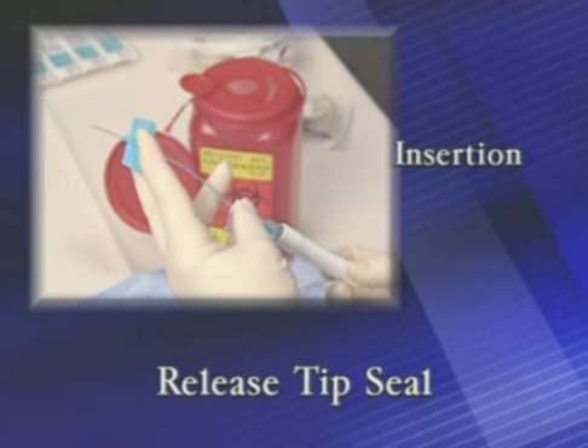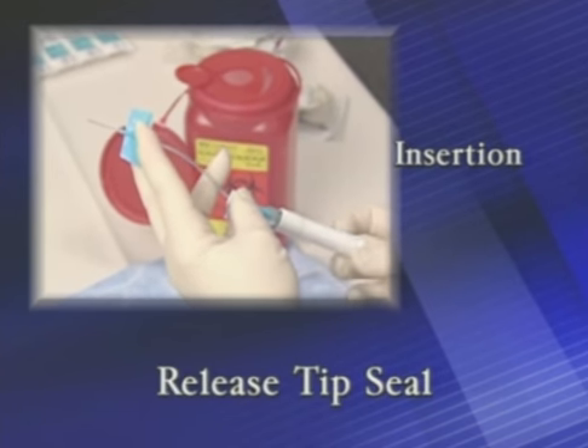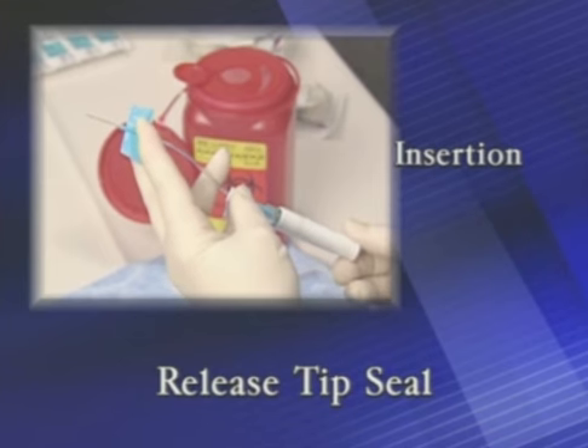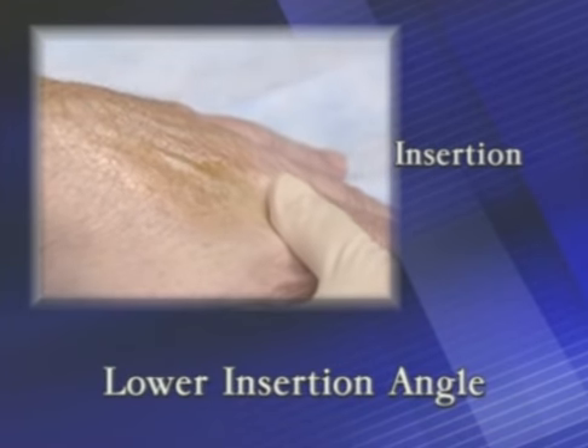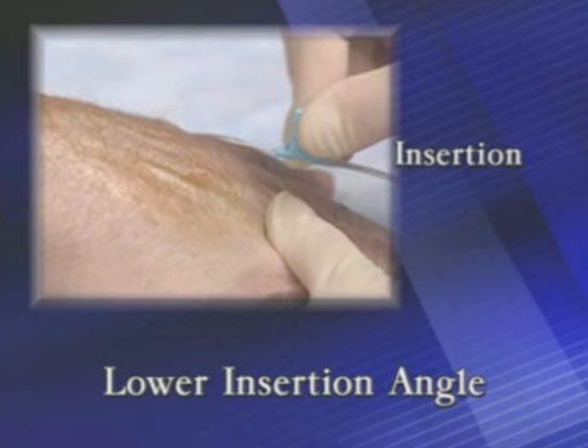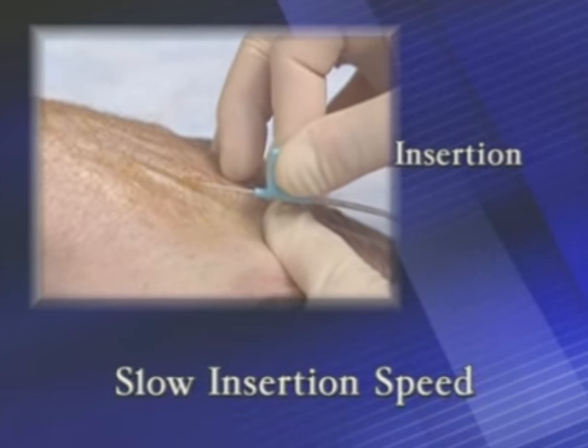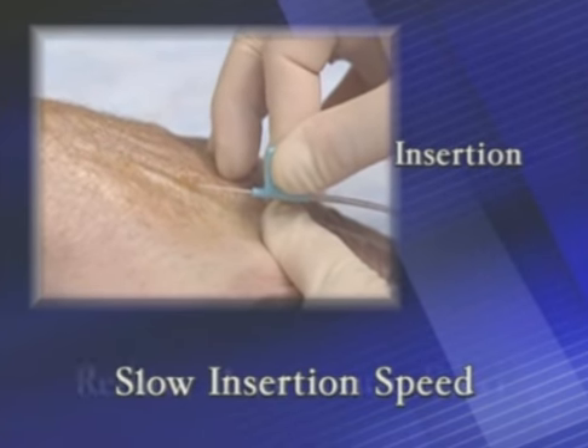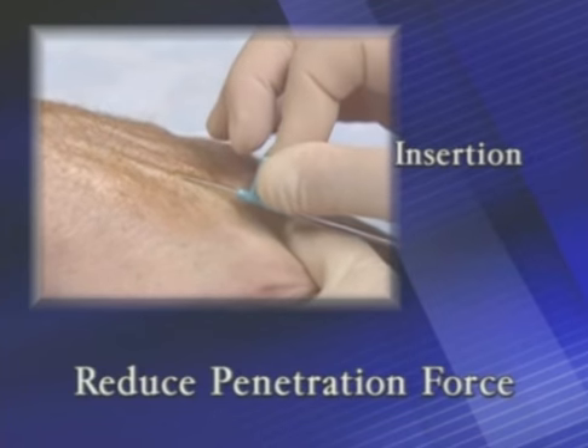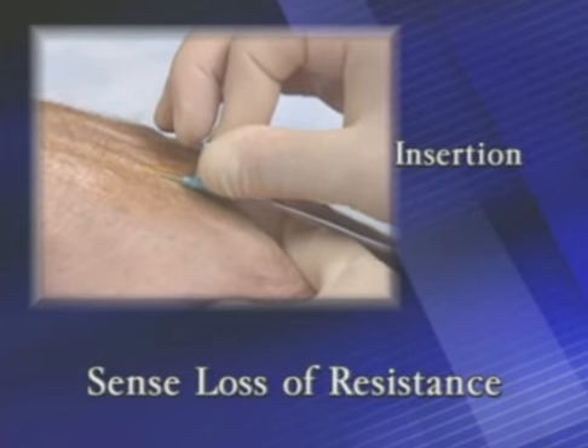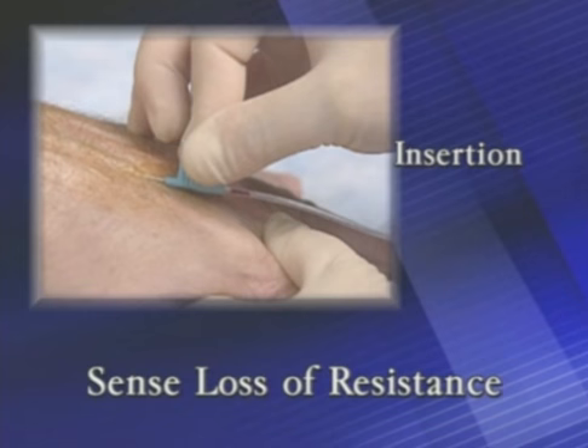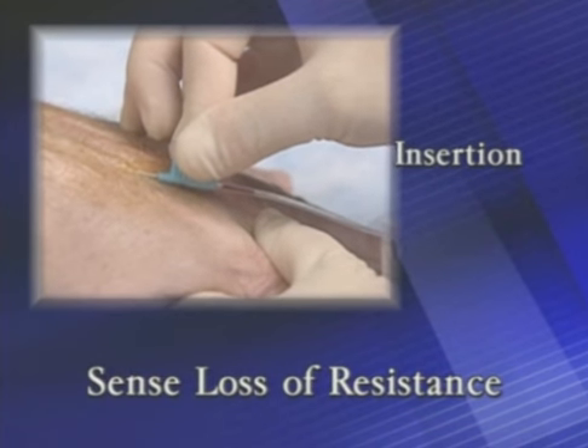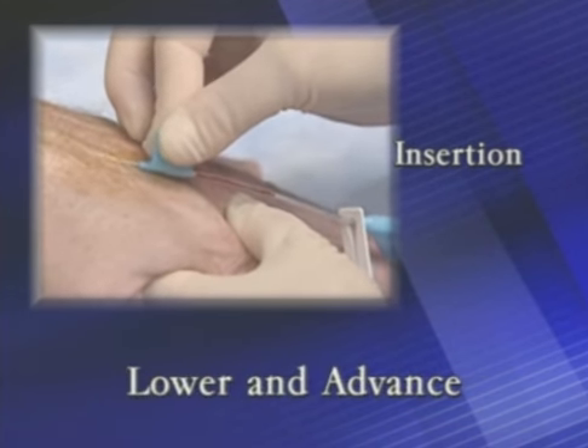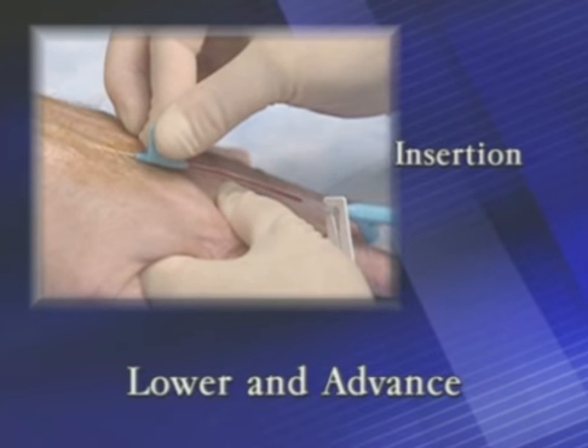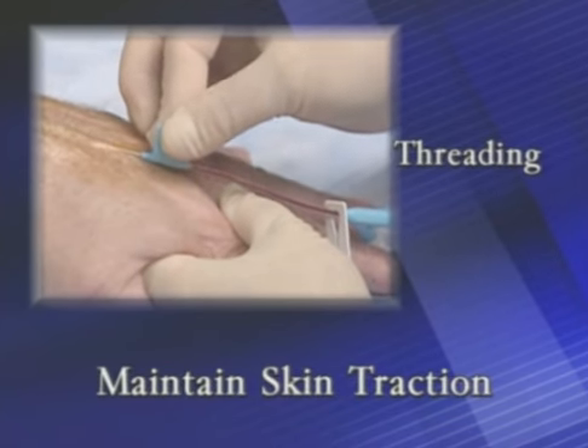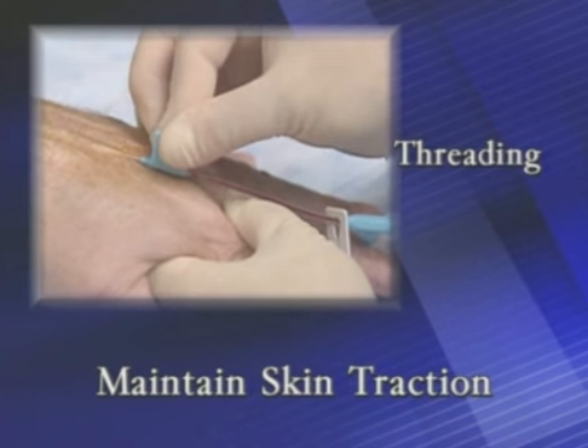Release the tip seal by holding the catheter as shown and rotating the safety shield clockwise. Lower your initial insertion angle so that the catheter is nearly parallel to the surface of the skin. Slow your initial approach to the vein. Reduce the force used to penetrate the skin. With BD catheters, you'll feel a loss of resistance rather than a pop when entering the vein. After visualizing flashback, lower the catheter angle and advance the entire unit forward slightly. Be sure to maintain traction on the skin as you're threading the catheter.